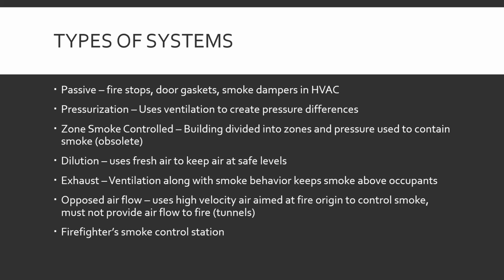And then firefighters' smoke control station. That's kind of like the command post we talked about earlier. But this one is strictly for the smoke systems. This will let firefighters say, all right, we like the ventilation. The ventilation is helping us. We'll keep the fire ventilation system on. We want to use the elevators. We'll turn off the fire curtains over the elevator doors, that kind of thing. It allows firefighters, trained people who know what they're doing, to pick and choose what systems to have on versus off.